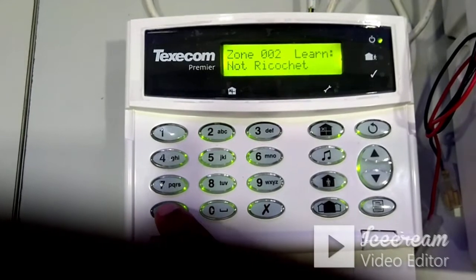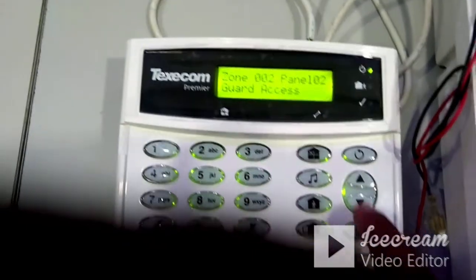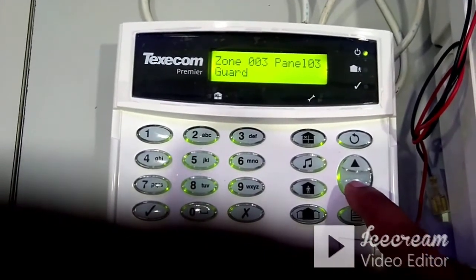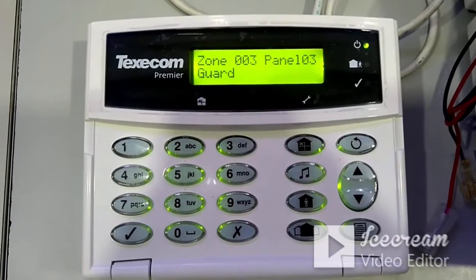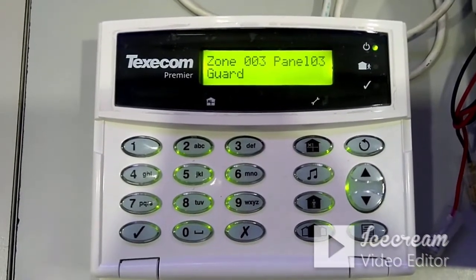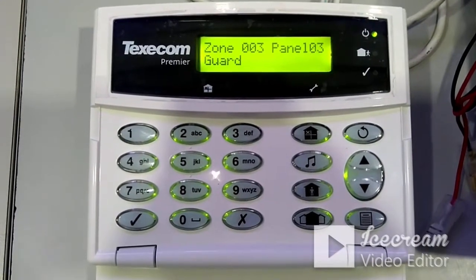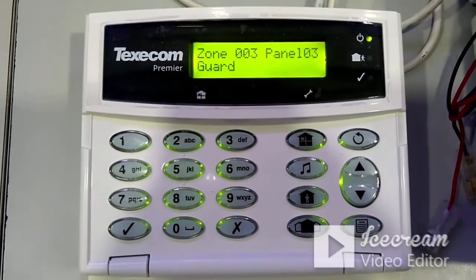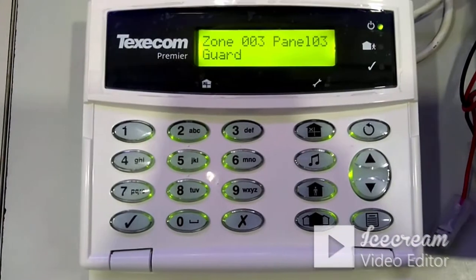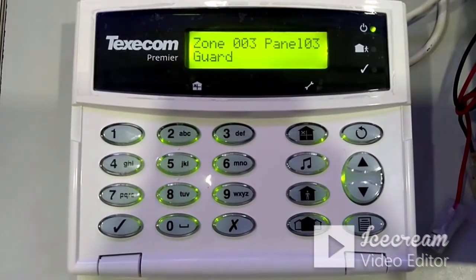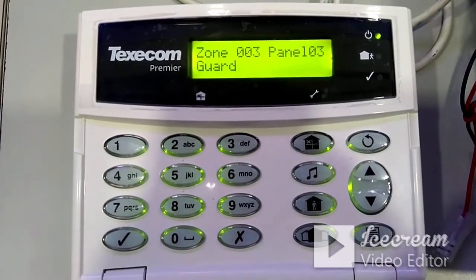For any zone programming, you only need to configure two or three settings: zone type and zone wiring type. Zone 2 programming is now complete. Moving to zone 3 — by default it comes as guard. The guard zone type means: if you arm the panel and the zone activates, the panel should go into alarm; if the panel is disarmed and the zone activates, the panel should not go into alarm. Those zones should be programmed as guard.